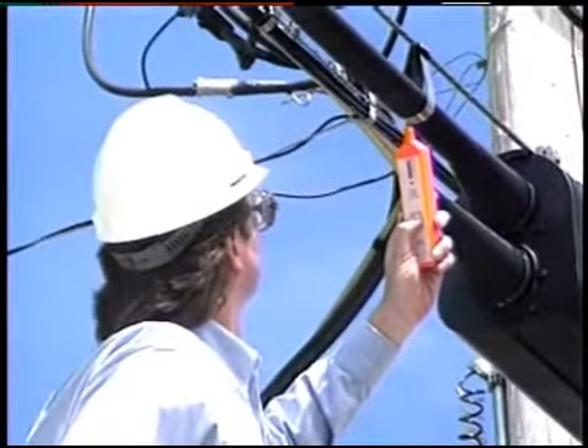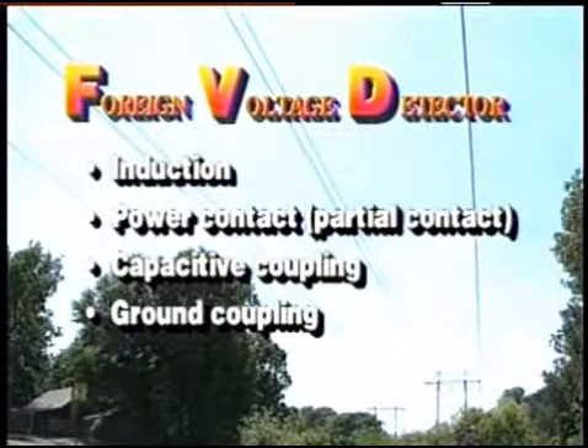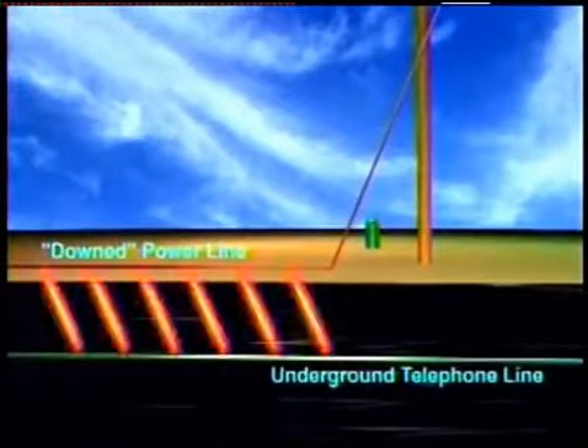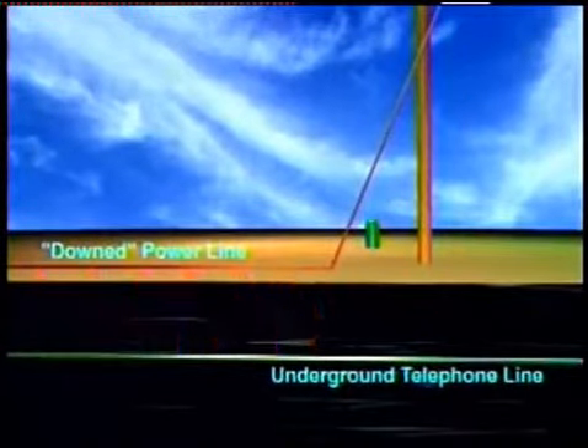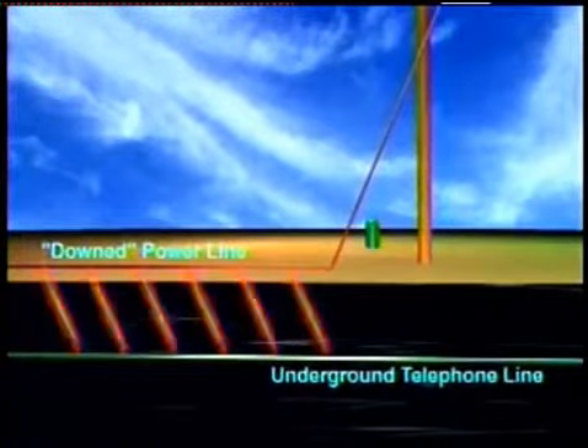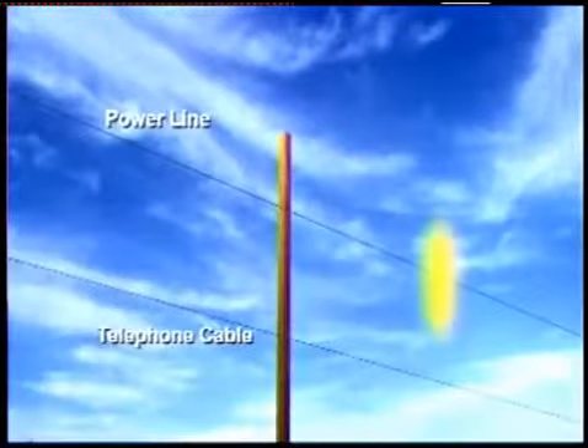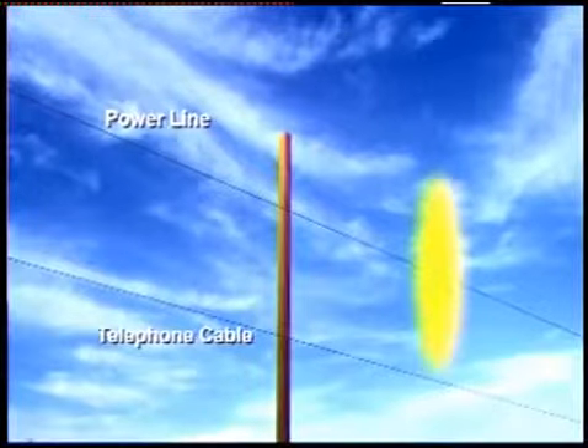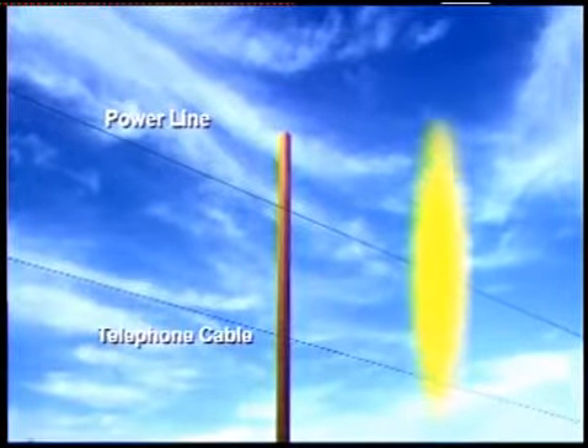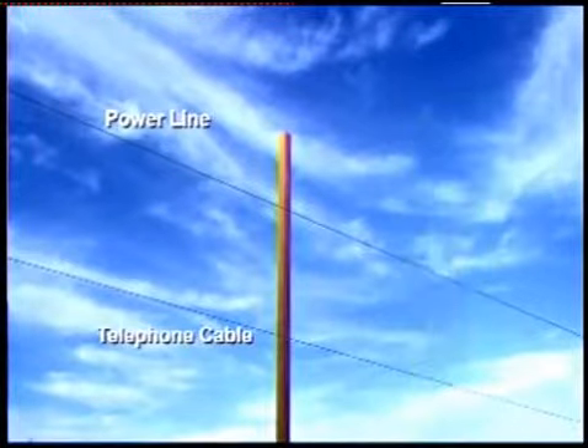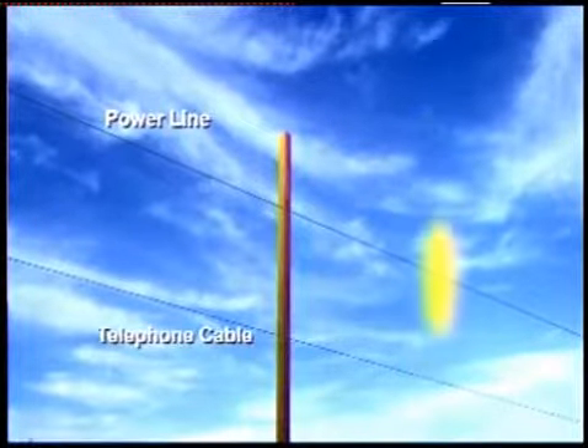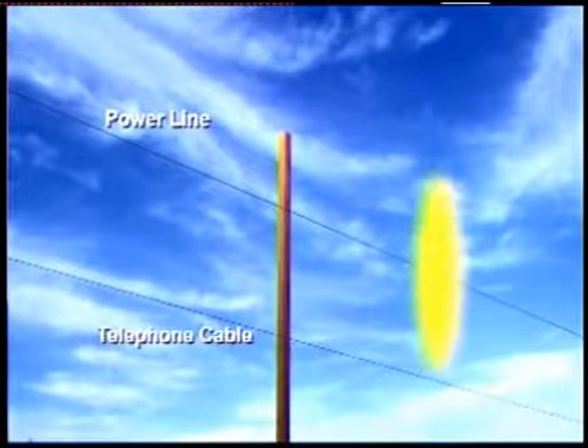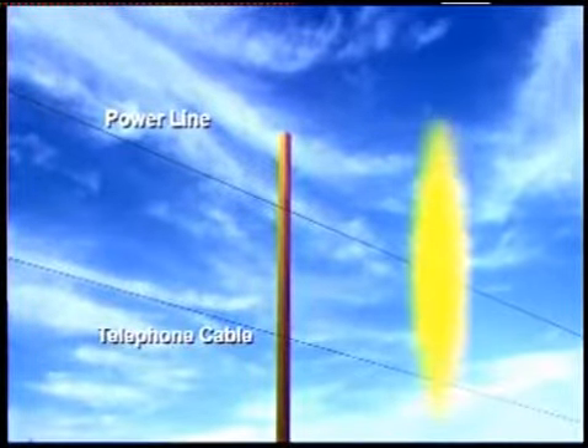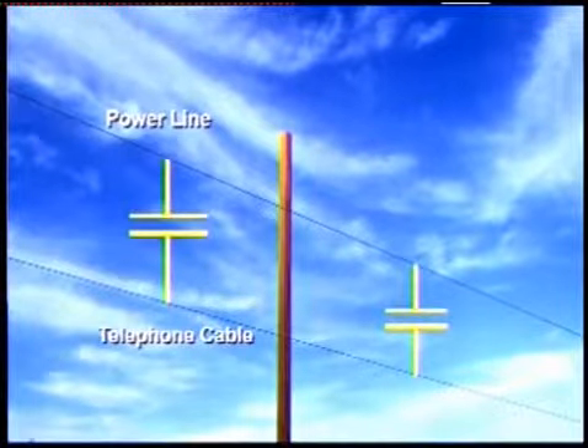There is often confusion over induction, power contact or partial contact, capacitive or E-field coupling, and ground coupling. Partial contact and ground coupling are similar and should be treated the same. If the voltage is at a hazardous level, either one can be dangerous. Inductive coupling occurs because of the magnetic field that surrounds a current-carrying conductor. It should be noted that this is the method used to produce electric power and to drive electric motors. The ability of induced voltages to produce current flow is then obvious, so it should be treated the same as contact and ground coupling. Capacitive coupling is different.